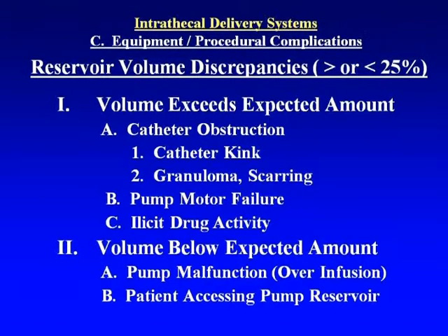It calculates it based on the rotation of the rotor - how much fluid is calculated to be pushed by the rotor with each rotation. You set it at a certain amount to be delivered, which gets internally interpreted into a number of rotations, and based on the rotations and how much fluid is pumped, that's how you get the value of the residual solution remaining.